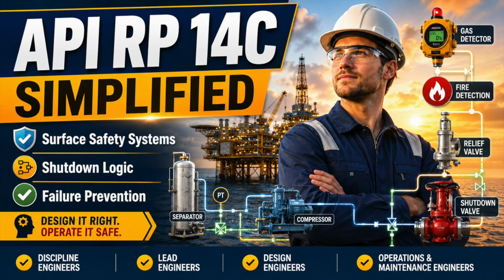Fired equipment requires even greater care because the process already contains an ignition source. You must manage process temperature, liquid level, circulation, combustion air, fuel pressure, flame proving, stack temperature, tube pressure, backflow, and safe startup sequencing. Flame failure must isolate fuel before unburned gas accumulates.